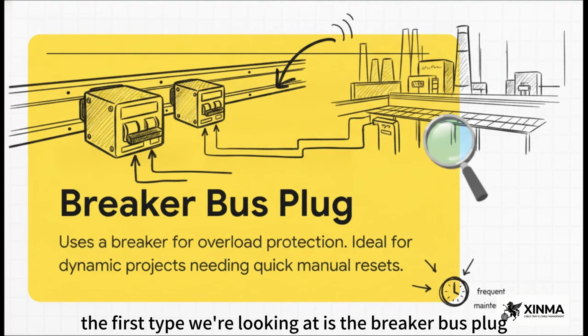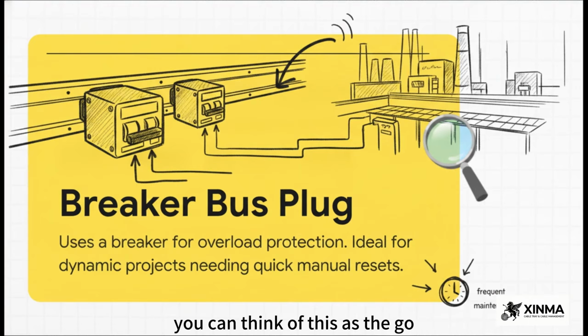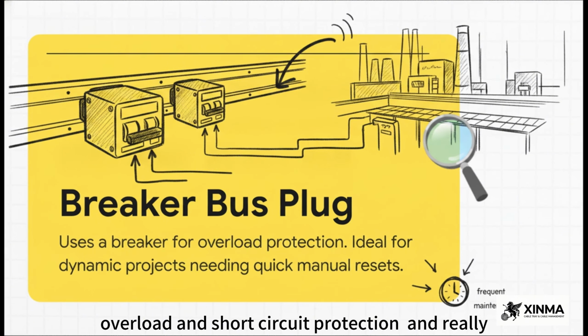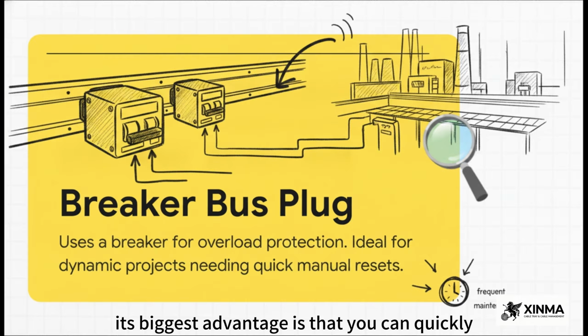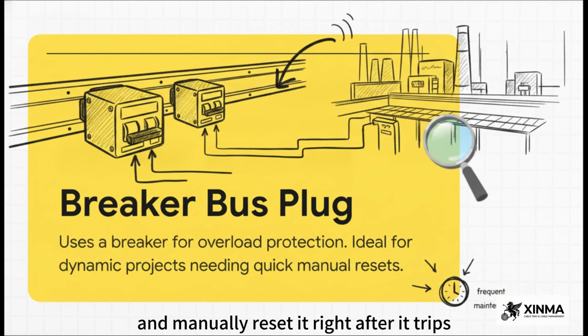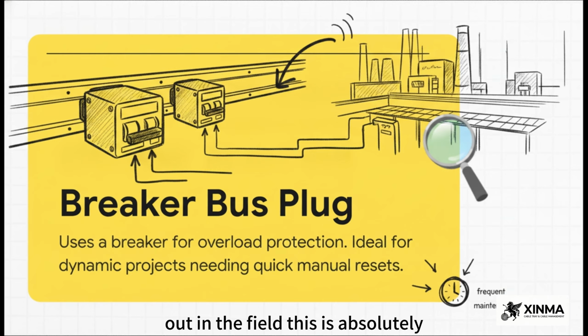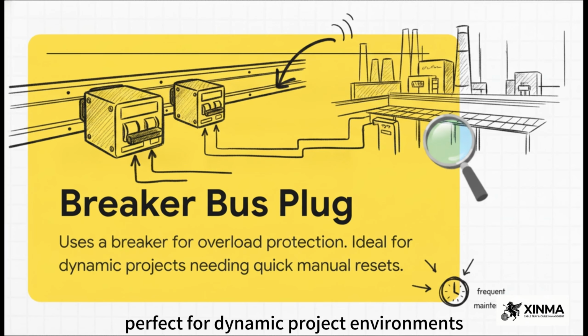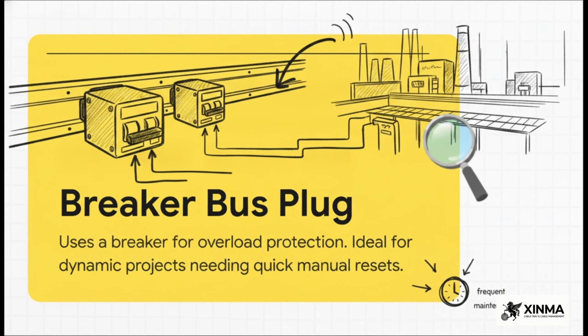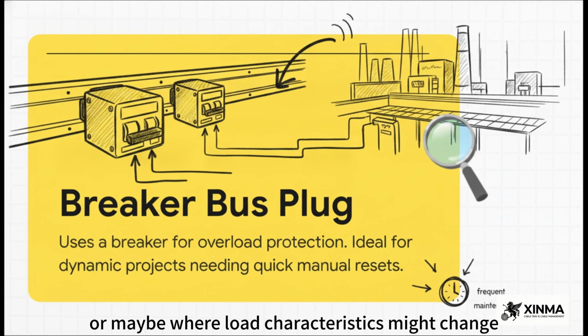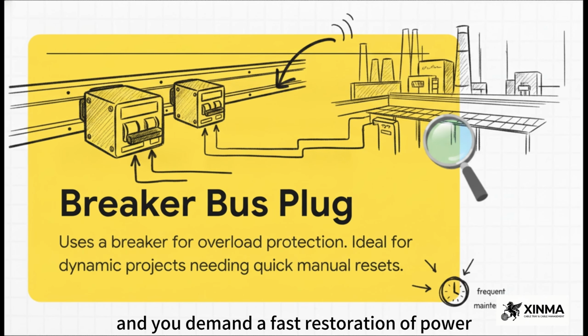The first type we're looking at is the breaker bus plug. You can think of this as the go-to option for most projects. It uses a circuit breaker for overload and short circuit protection. And really, its biggest advantage is that you can quickly and manually reset it right after it trips. Out in the field, this is absolutely perfect for dynamic project environments, places that require frequent maintenance, or maybe where load characteristics might change and you demand a fast restoration of power.